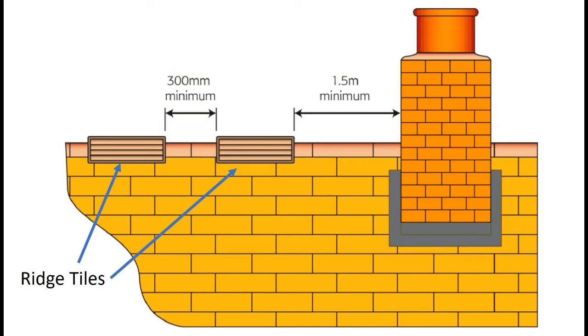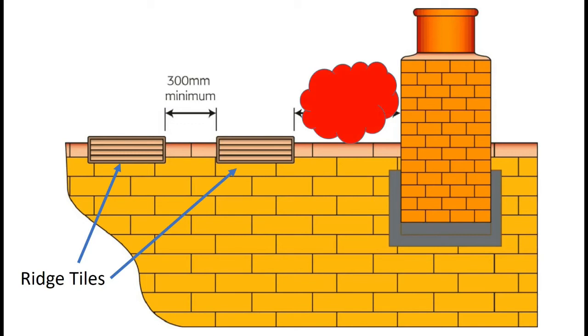In this picture, here are two ridge tiles, and as you can see there are minimum distances between them and a 1.5 metre minimum from the chimney. The reason the chimney comes into play is because whatever way the wind is blowing it will create a different pressure zone within the area of the red clouds. These will have little pressure zones all of their own and, as we learned from the previous video, we need to keep terminals outside of these pressure zones.